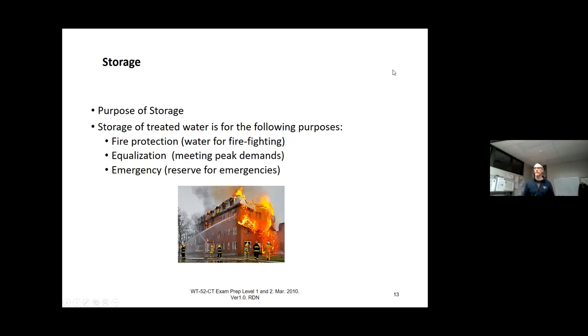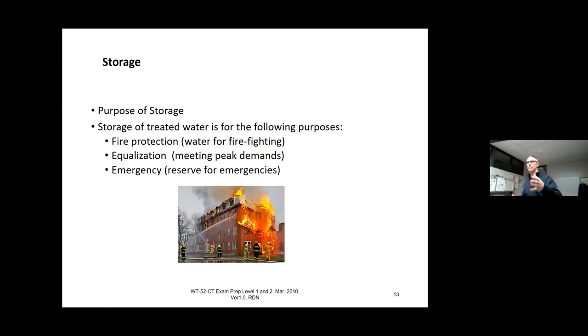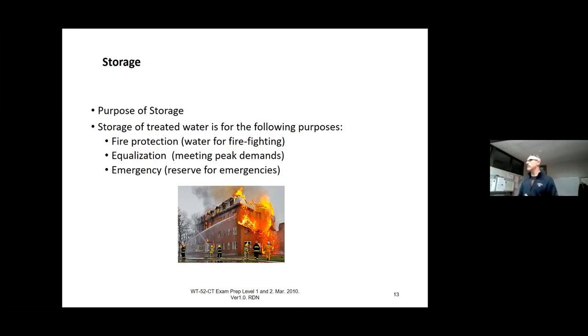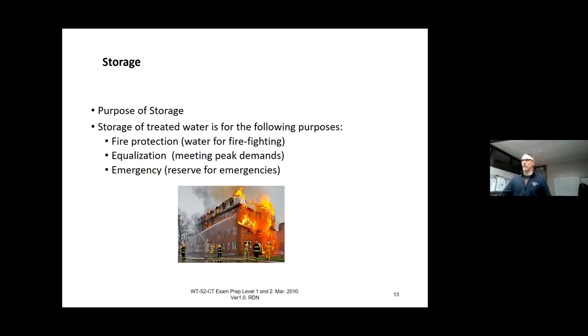So why do we do storage? These are the three big ones, and when they ask you on the test, these are the answers. Storage is done for fire protection, for equalization of peak demand, and for emergency — a reserve for maintenance, main breaks, fires, or anything else. You have to look at your customer, look at what your infrastructure looks like, and plan for all three of these events. This is the main purpose of water storage.